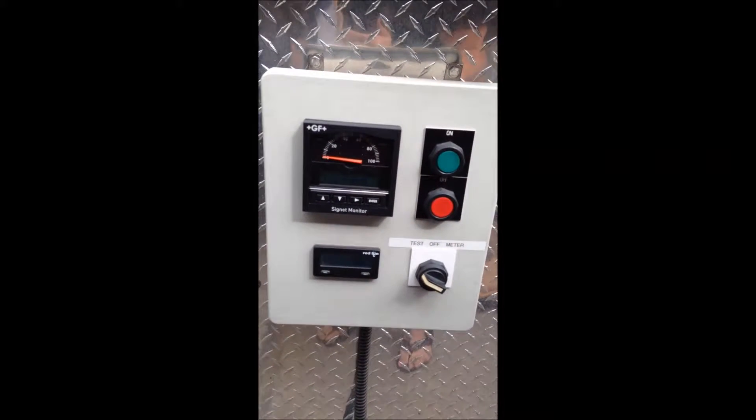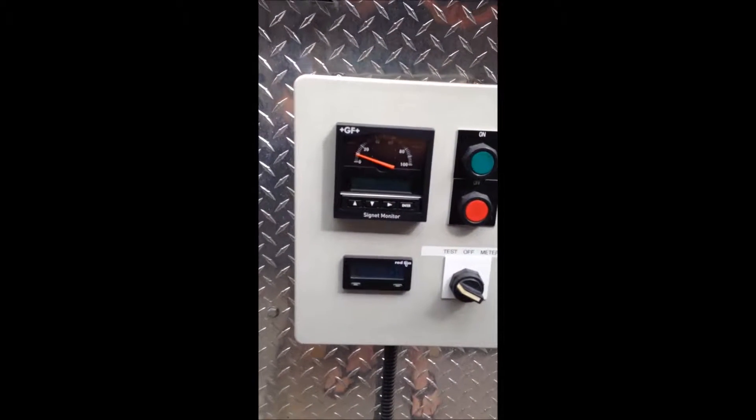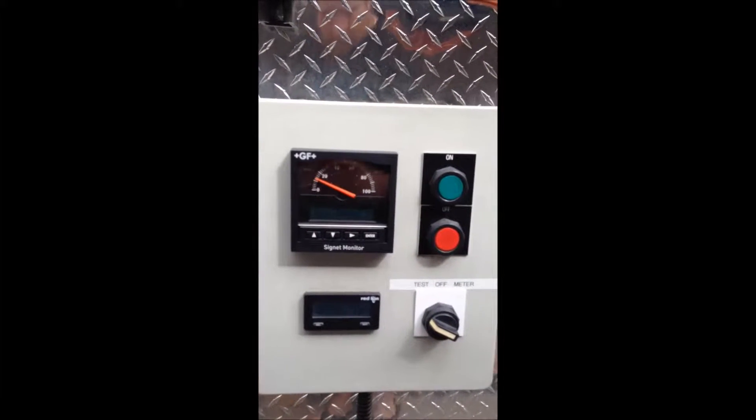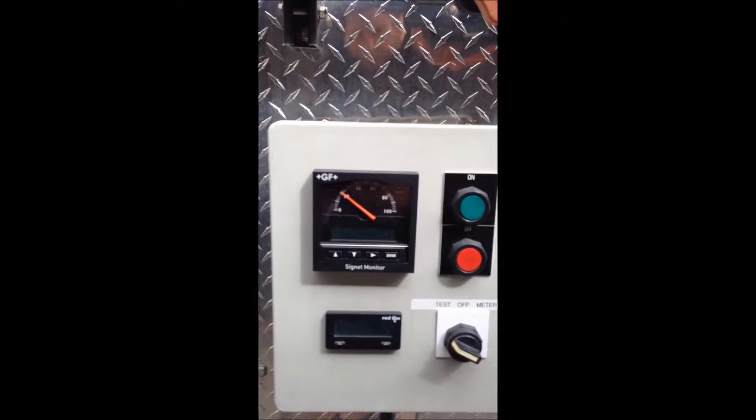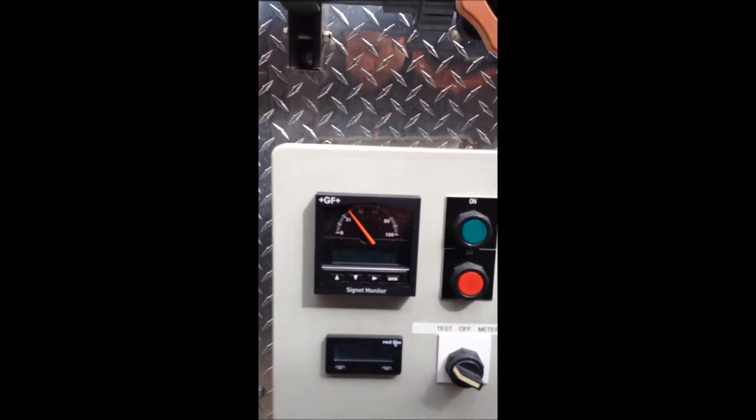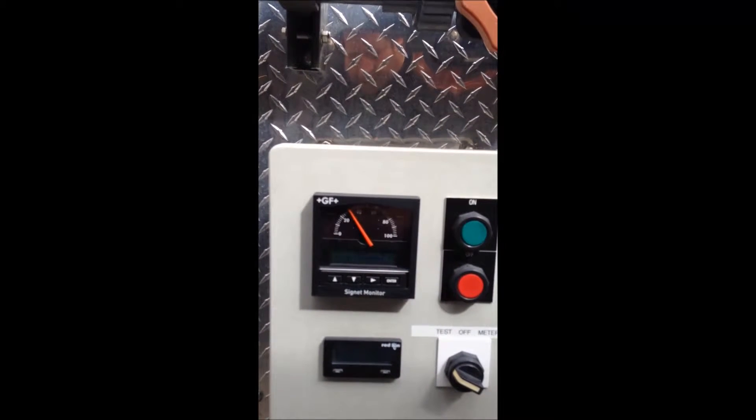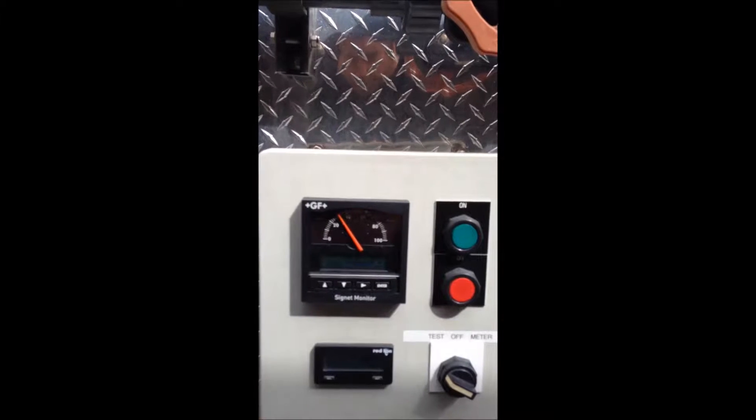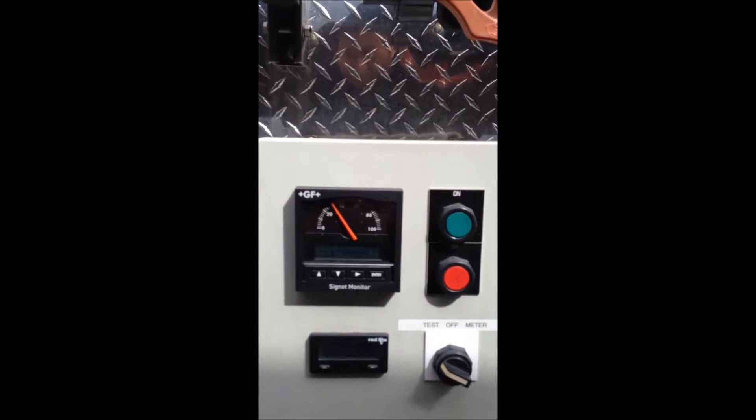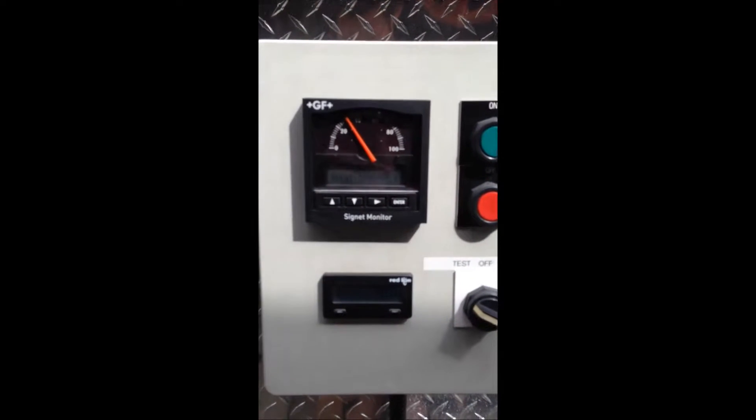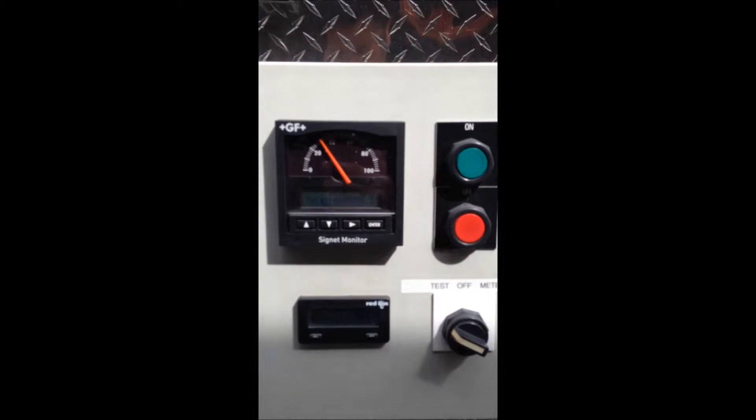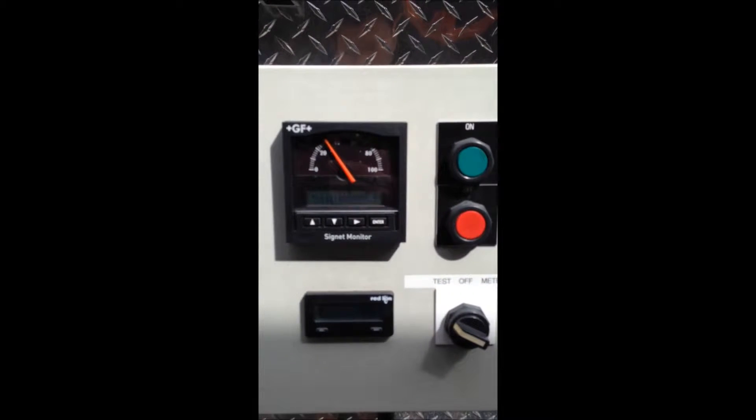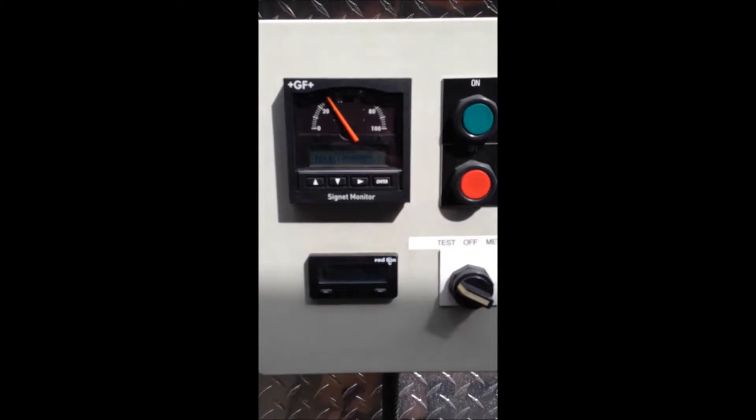We'll start our test. You'll see that our volume on this pump is locked in at approximately 31.5 gallons per minute. We'll bring you back to the test results as soon as the 5-minute cycle is complete.